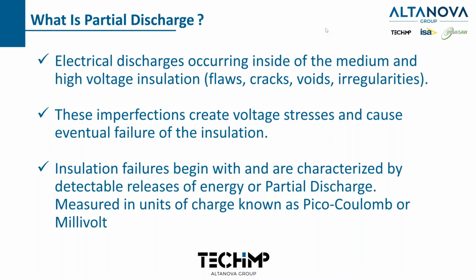and also in water trees. Water trees are basically microvoids in a cable that's been energized for a period of time with the current flowing through it. Water trees will develop in the cable, and how it happens is water diffuses in the insulation. It causes these water trees. And water trees aren't inherently dangerous to an insulation, although it is a degradation of the insulation, but it won't fail the cable.